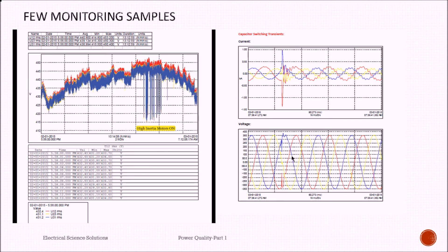Here this graph shows capacitor switching transients. Now you can see the load is in kiloampere. The load is very smooth, but as soon as there is a switching of the capacitor, it took a very high rise in a current, and at the same time you can see the problems in the voltage. Now these sharp dips can impact a sensitive equipment like electronics, ballast, or a lot of electronic things.